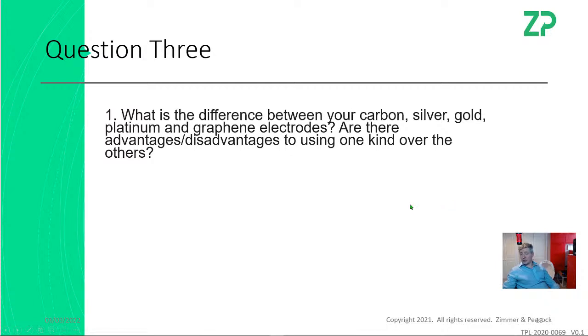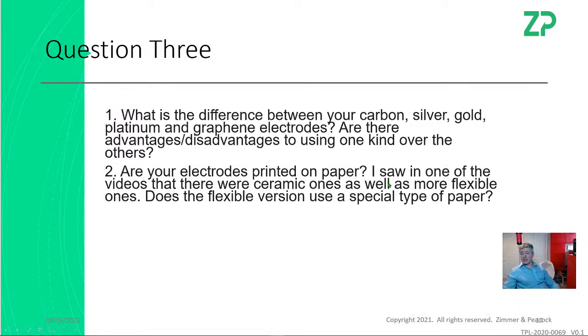So my choice these days is carbon. I'm sure graphene is good, it's just the cost of production of graphene that's the big issue. And I used to suggest gold for making immunosensors, because with gold you can make a self-assembled monolayer. From a self-assembled monolayer you could then attach the antibodies. But honestly these days I just say use this strategy I showed earlier on, which is use that pyrene NHS linker and skip the idea of gold, just go straight to carbon.